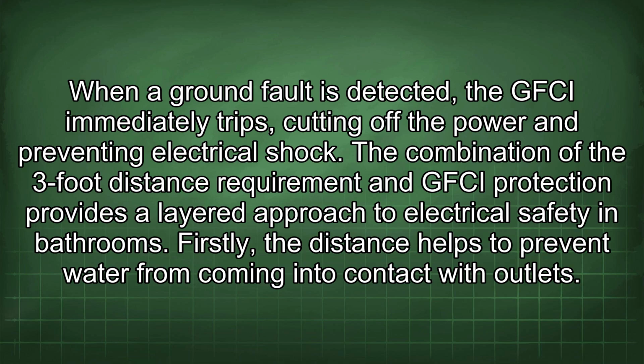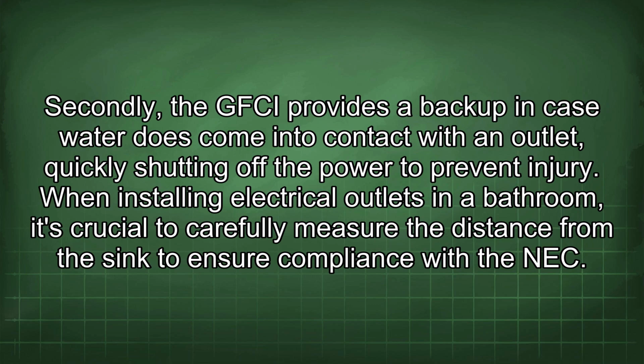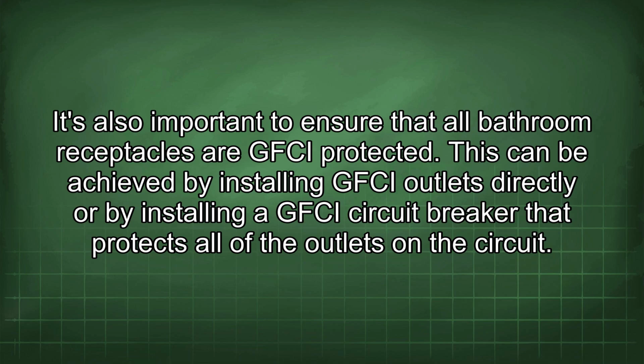The combination of the 3-foot distance requirement and GFCI protection provides a layered approach to electrical safety in bathrooms. Firstly, the distance helps to prevent water from coming into contact with outlets. Secondly, the GFCI provides a backup in case water does come into contact with an outlet, quickly shutting off the power to prevent injury. When installing electrical outlets in a bathroom, it's crucial to carefully measure the distance from the sink to ensure compliance with the NEC. It's also important to ensure that all bathroom receptacles are GFCI protected. This can be achieved by installing GFCI outlets directly or by installing a GFCI circuit breaker that protects all of the outlets on the circuit.